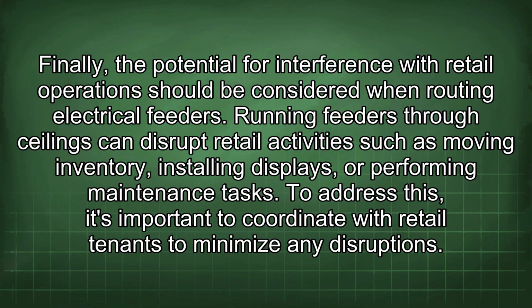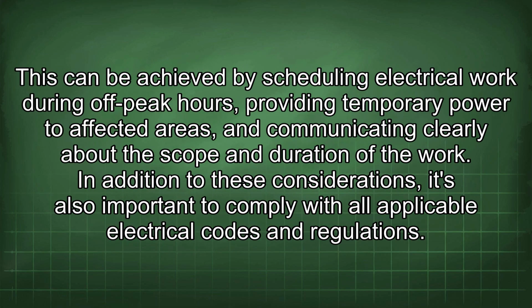Finally, the potential for interference with retail operations should be considered when routing electrical feeders. Running feeders through ceilings can disrupt retail activities such as moving inventory, installing displays, or performing maintenance tasks. To address this, it's important to coordinate with retail tenants to minimize any disruptions. This can be achieved by scheduling electrical work during off-peak hours, providing temporary power to affected areas, and communicating clearly about the scope and duration of the work.